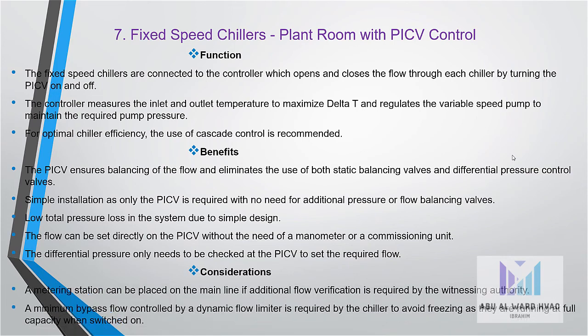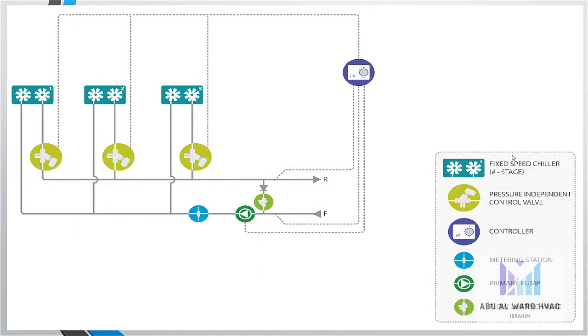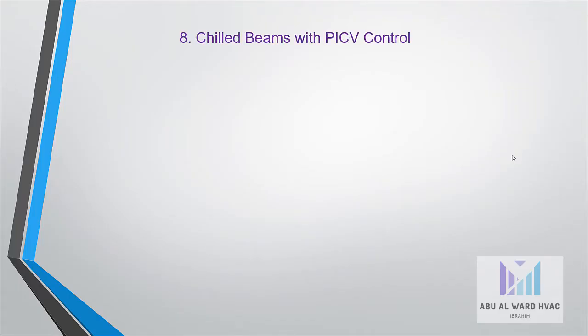Considerations: a metering station can be placed on the main line if additional flow verification is required by the witnessing authority. A minimum bypass flow control by a dynamic flow limiter is required by the chiller to avoid freezing, as they are running at full capacity when switched on. And this is the schematic for this case.